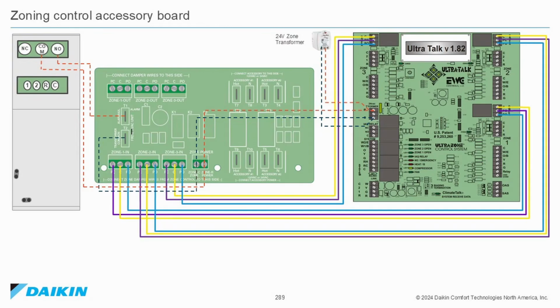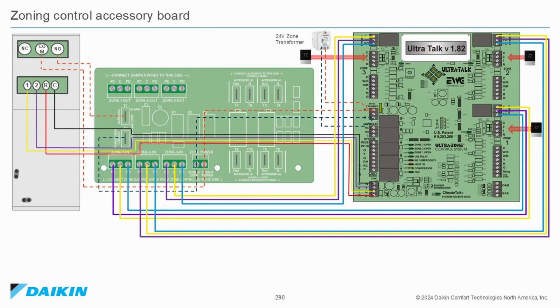Wires should also be routed from the zoning control accessory board, terminals Zone 1, 2, and 3 in, to the EWC control module damper connections 1, 2, and 3. Terminals R and C and communication wires 1 and 2 should also be routed from the indoor unit control module to the EWC control module, terminals C, R, 1, and 2. Wire the 3 zone controllers to terminals C, R, 1, and 2 on the EWC control module. Then route wires from the zoning control accessory board, terminals Zone 1, 2, and 3 out to the 3 damper motors for zones 1, 2, and 3.